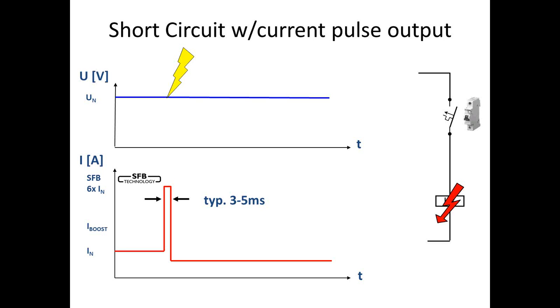A designer can either select a standard power supply sized to trip the breaker or use a supply that's able to provide a breaker tripping current pulse. This pulse is 6 times the nominal rating of the power supply and lasts for a duration of 3 to 5 milliseconds. A 5-amp power supply with a current pulsed output can provide a 30-amp pulse to trip breakers. And this is certainly a value proposition.